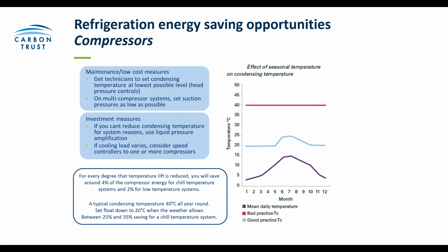Compressors. So again, this is where all the heavy work is done in your refrigeration system. So you can make really big impacts here if you make it easier for the compressor to do its job. So this is the part of the system that is working to raise pressure and therefore the temperature above the ambient temperature in order for heat to be rejected. So get your technician to set the condensing temperature to the lowest practical level. And once that limit is reached, it may be possible to upgrade the control valves that you have or condensing capacity to allow further reductions.